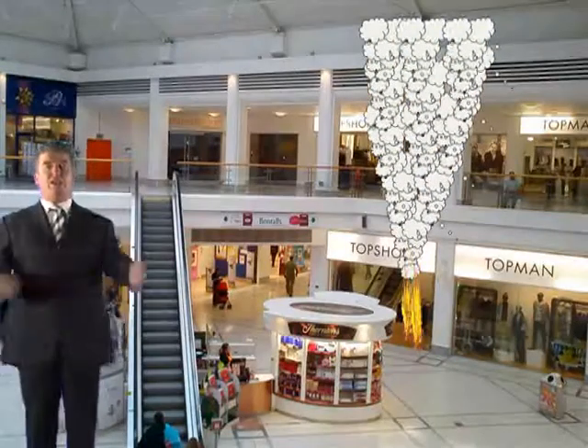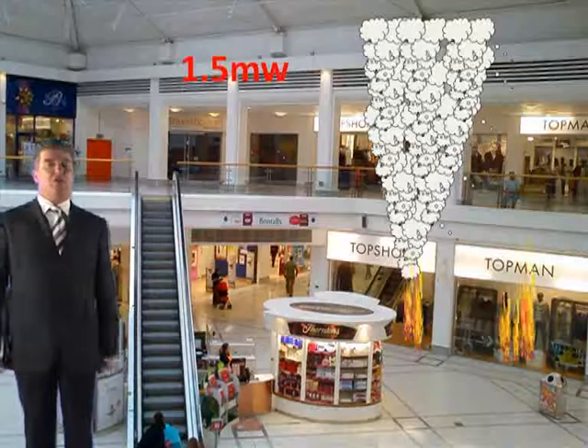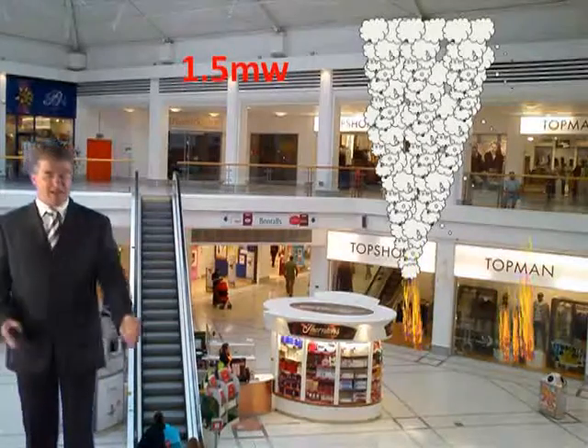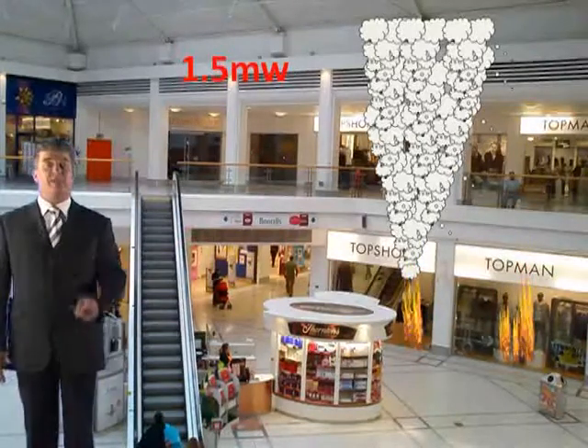For example, if they design a shopping centre or an atrium and they're saying, right, well, you're going to use a 1.5 megawatt fire in the main area, on the shops, for example. Well, that's not reasonable. Where do you get a 1.5 megawatt fire from? Well, it's very favourable to our calculations. Well, it might be favourable to them, mate. You're not going to limit that in the shops, are you? The shops will not have that fire growth rate. You'll not have a 1.5 megawatt fire. It's unreasonable.